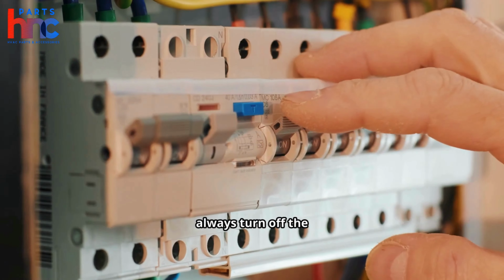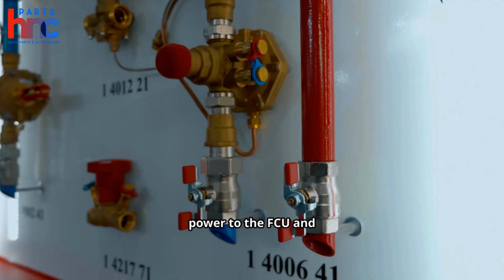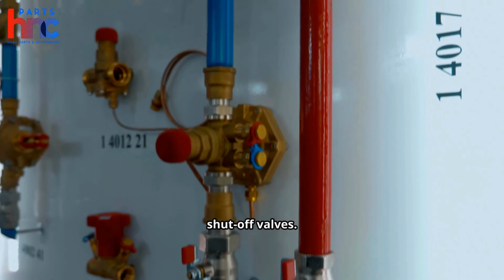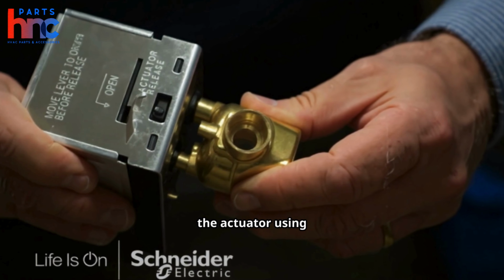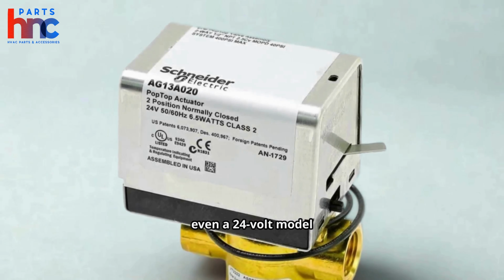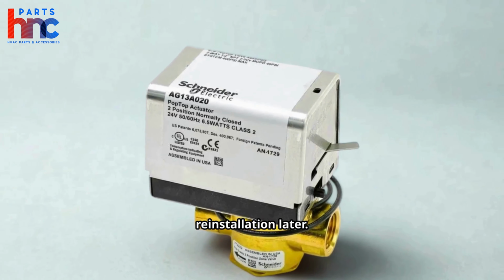Before installation, always turn off the power to the FCU and close both the supply and return shutoff valves. Start by removing the actuator using the release button. Even a 24-volt model detaches easily for reinstallation later.